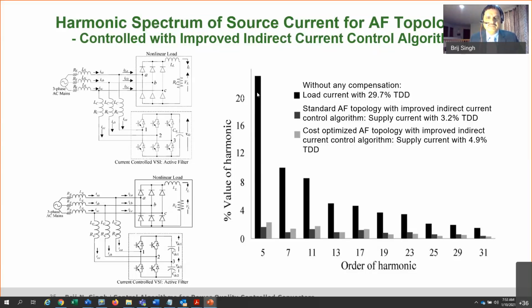So if you eliminate these two with a passive filter, the remaining harmonics would be much less. You could design a passive filter using a 7th and 5th harmonic tuned LC filter. Actually it's not exactly LC but RLC, since you need a little resistance to add damping and prevent oscillation from the LC elements, making it a critically damped system.